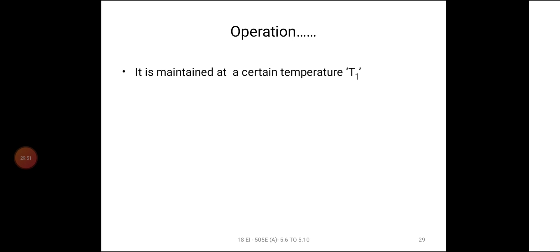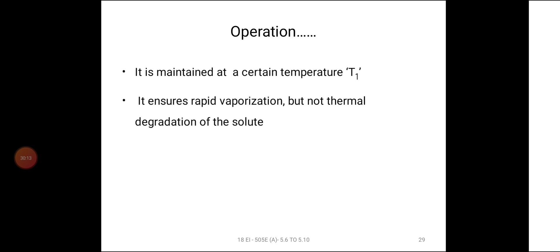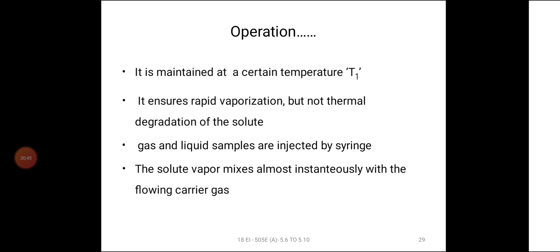The sample injection port is maintained at a certain temperature, T1. This ensures rapid evaporation but not thermal degradation of the solute. Gas and liquid samples are injected by syringe. The solute vapor mixes almost instantaneously with the flowing carrier gas. That means the sample is carried by the carrier gas into the column. It is swept into the chromatographic column.